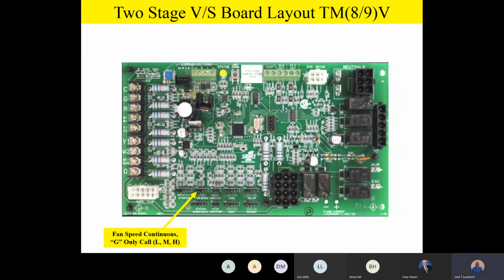Okay, below the fan speed, you have your blower delay jumper, and that's used for your heating off delay. Remember, team, all of our Champion furnaces have a 30-second on delay in the heating mode. Once you get flame proving, 30 seconds later the fan comes on and you distribute heat into conditioned space. However, the off delay timing is field selectable. How long does the fan run after the call for heat goes away? That's that blower delay jumper right there, your heating off delay jumper.